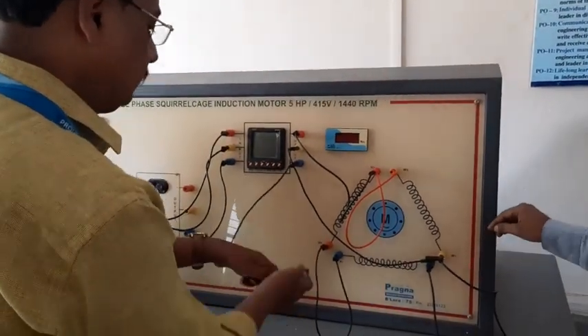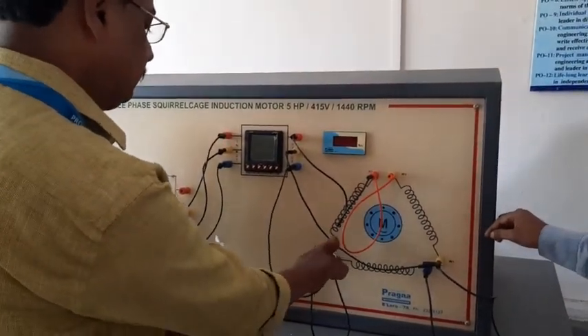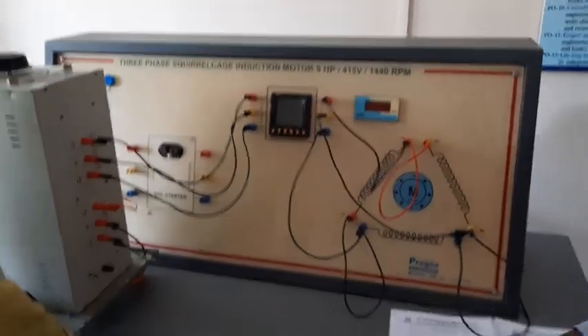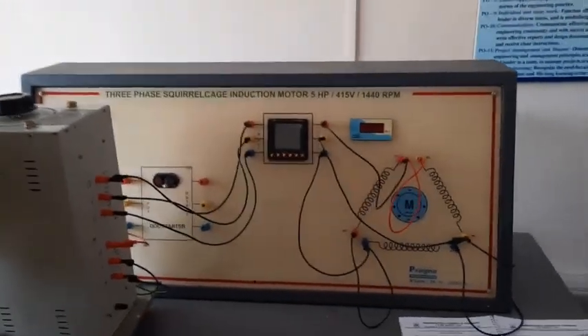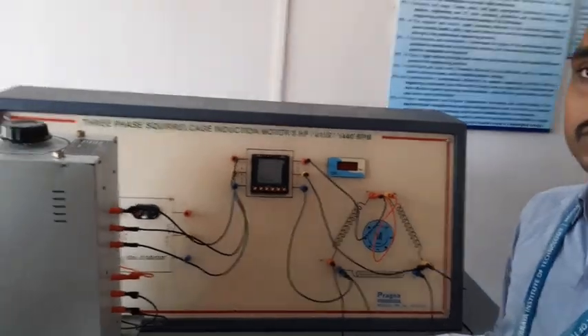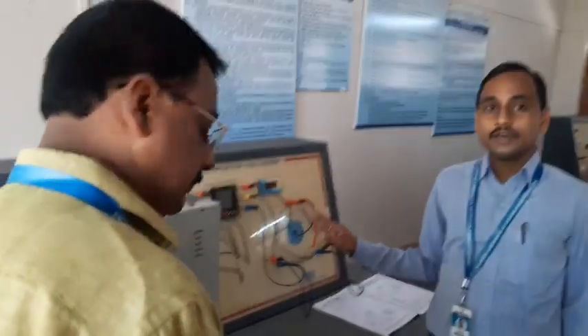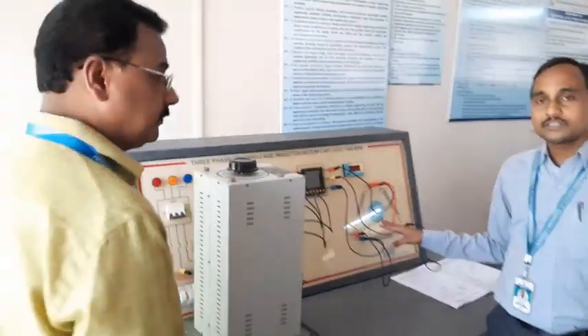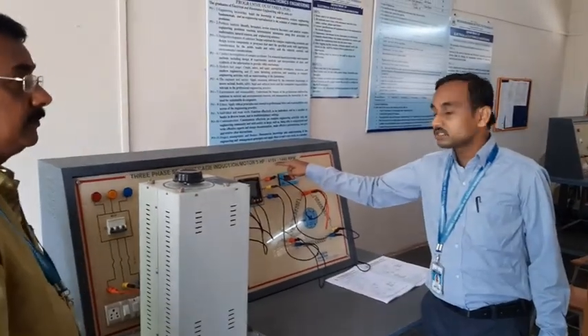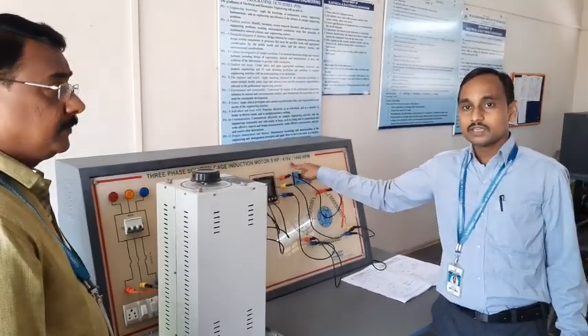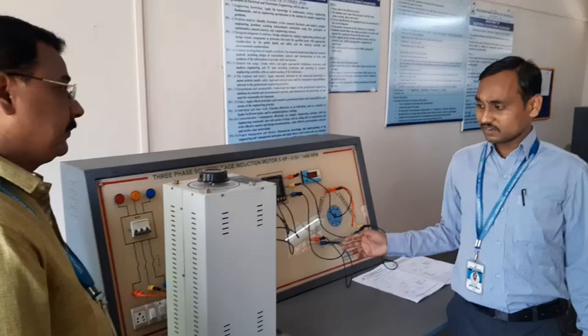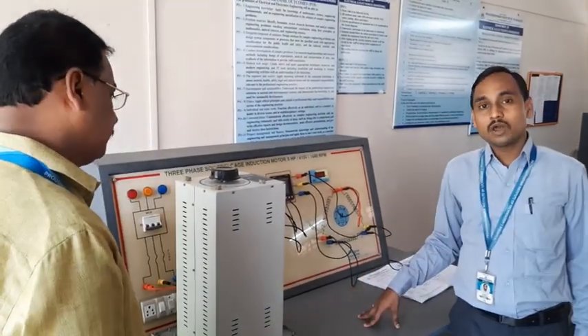B phase to the B phase. So in this experiment, the procedure is, first we have to conduct the no load test. In that no load test, we have to apply the rated voltage of the 3-phase induction motor. The rated voltage is 415 volt. After that, again you have to conduct the experiment for the blocked rotor test.